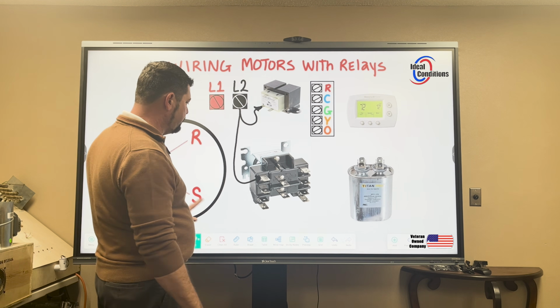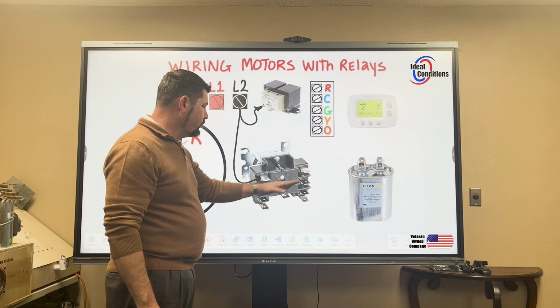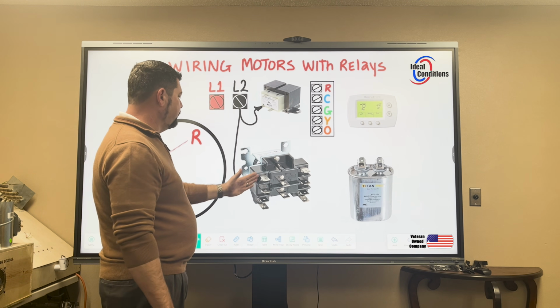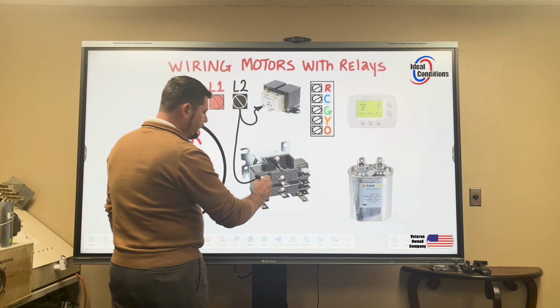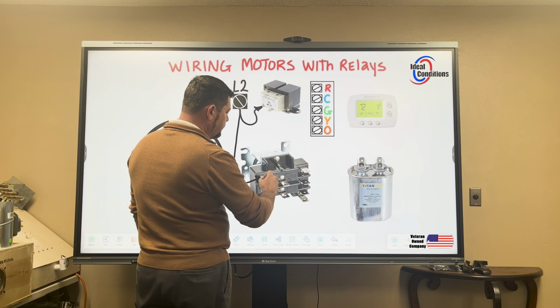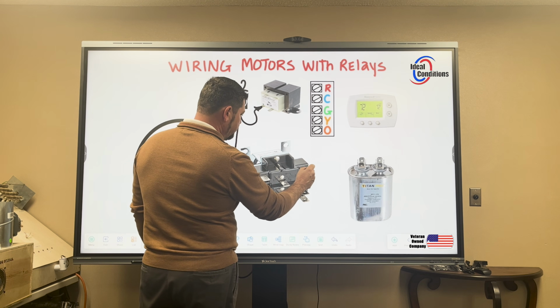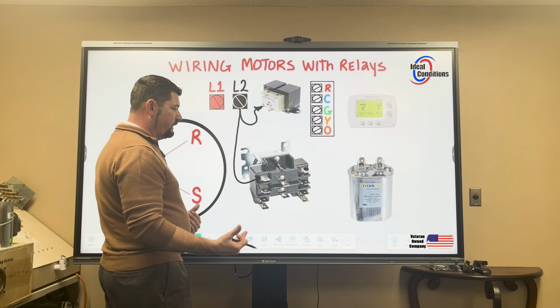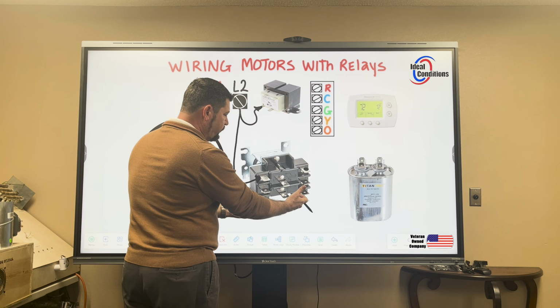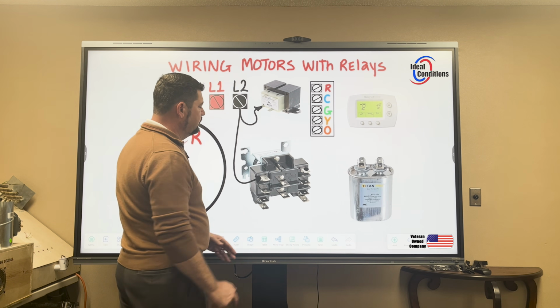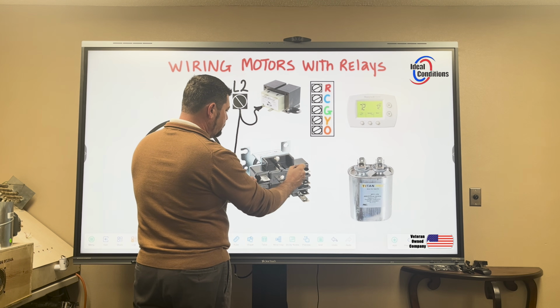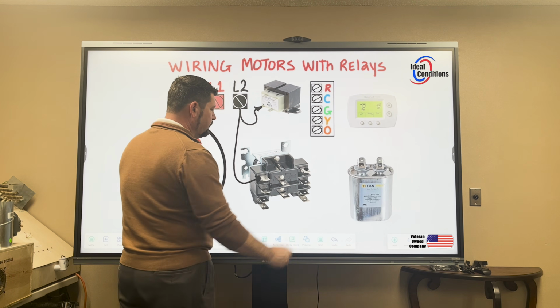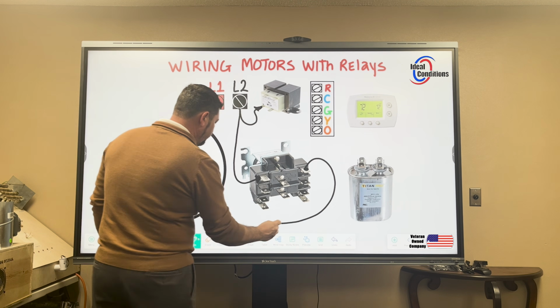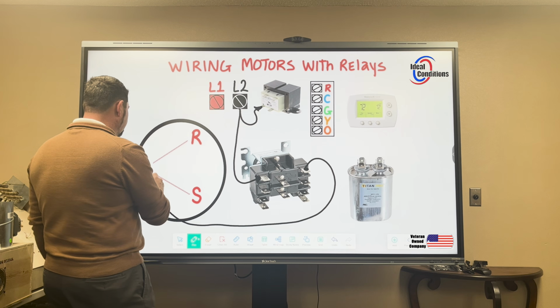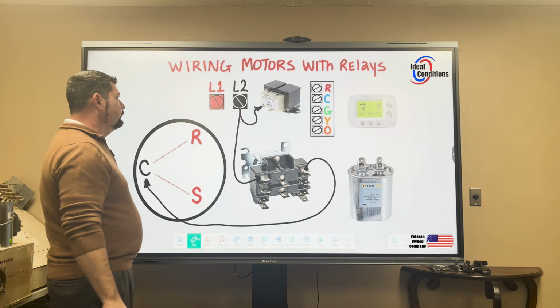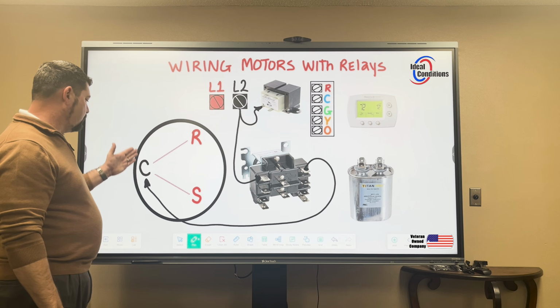Just to bring this fan motor on, I only need to work on one pole—I don't have to work on the second pole. The only other thing that needs to happen is coming over to my normally open terminal, which is terminal 3. That means 3 isn't running unless I have 24 volts present at the bottom of my relay. Once that's present, the normally open contact will close, terminal 3 will make, and we'll have L2 supplying power on our common winding.